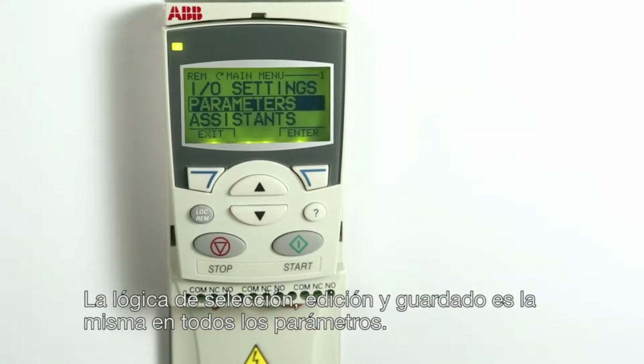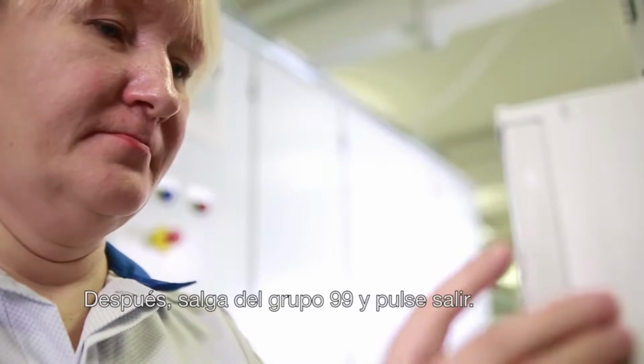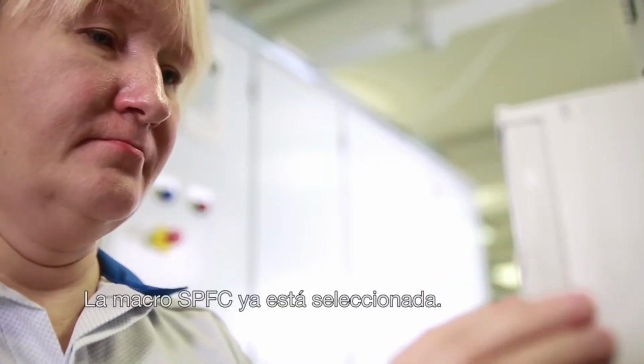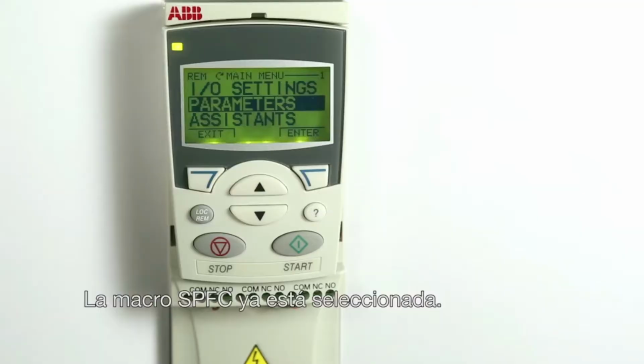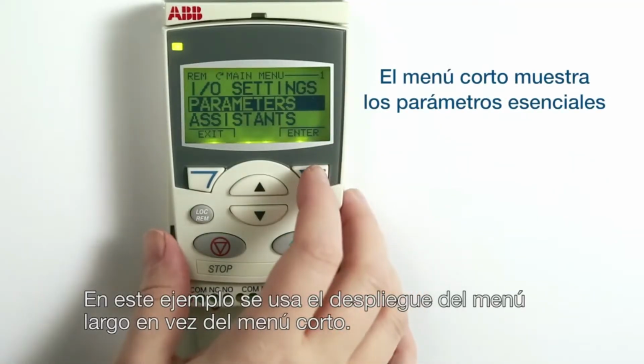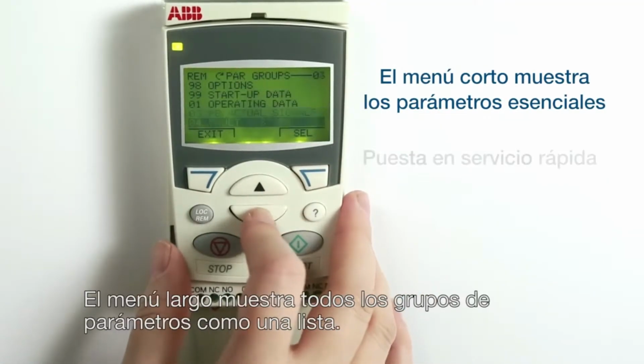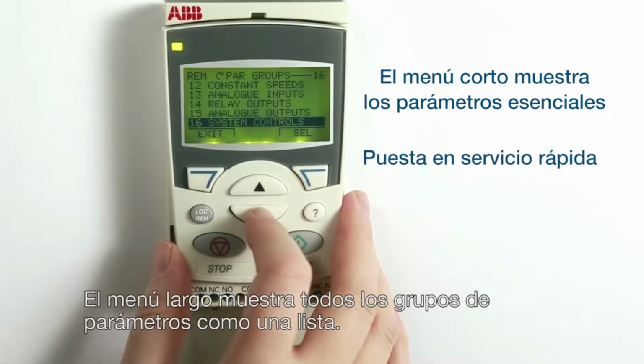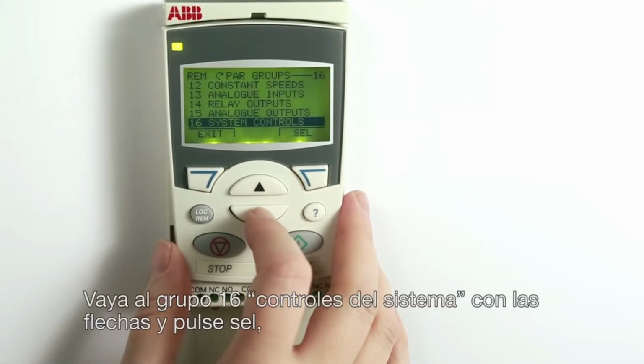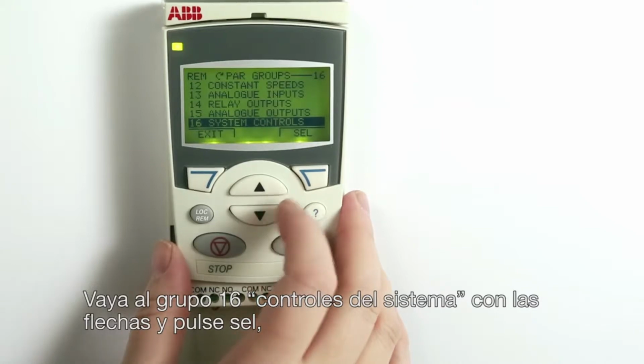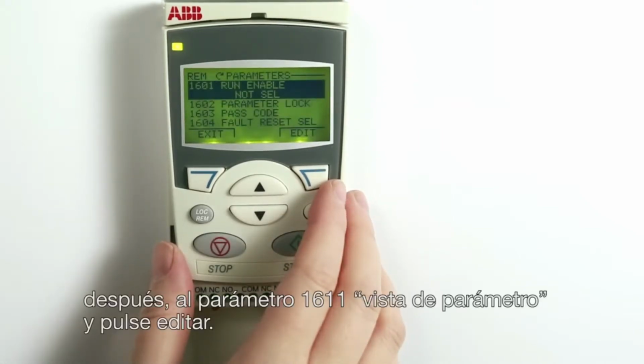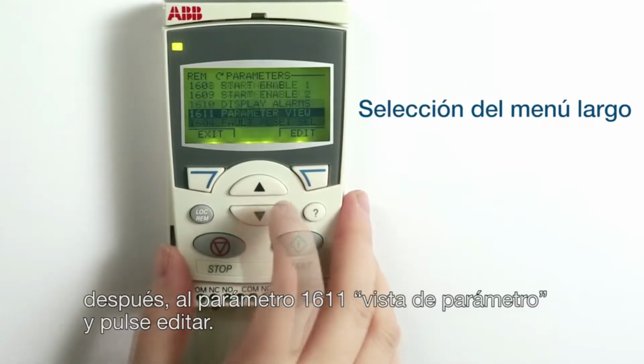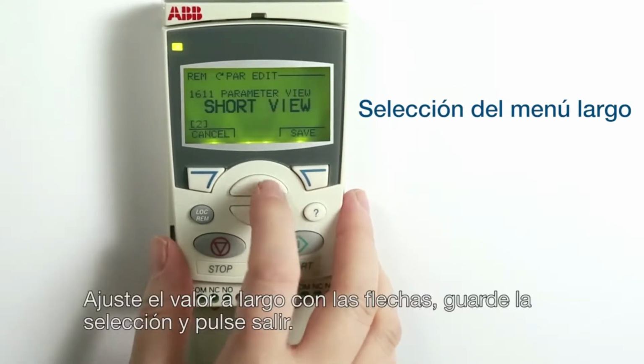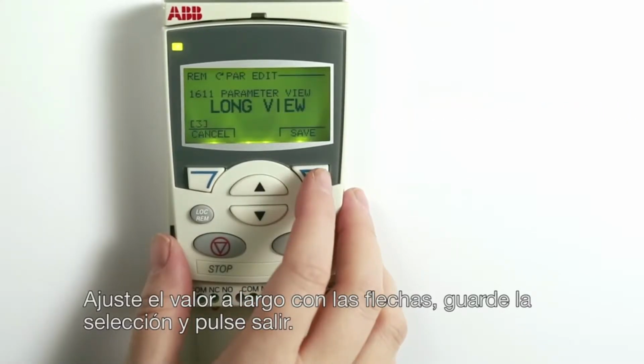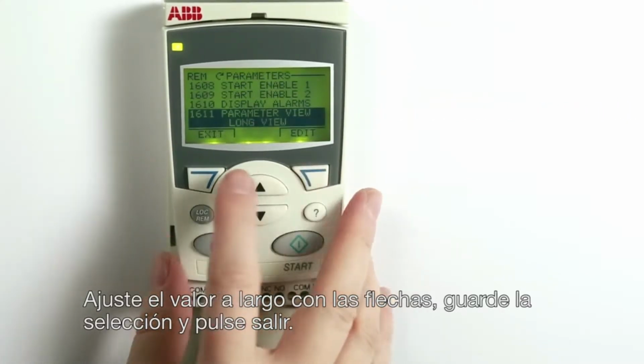The logic of the selection, editing and saving is the same for all parameters. Then we leave group 99 and press Exit. Now the SPFC macro selection is done. In this exercise, we use the long menu display instead of the short menu. This long menu shows all the parameter groups as a list. We go to parameter group 16, System Controls, with arrow keys and press Select. Then to parameter 1611, Parameter View, and press Edit. Then we change the value with arrow keys from short to long. Save the selection and press Exit.